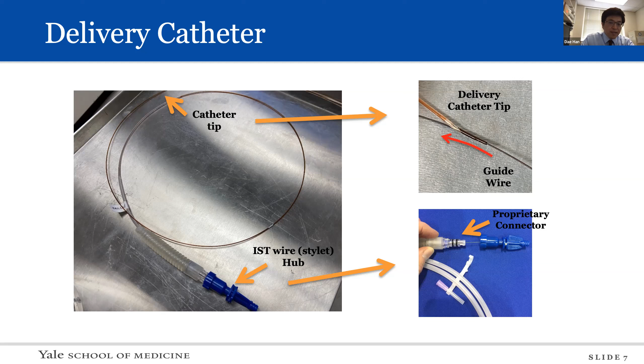And this is the operation mechanism. The delivery catheter has coaxial dual wall lumens. So when we press the syringe, water will push the source from the proximal to the distal direction, and once the source reaches the end of the catheter, there is a mesh structure that blocks the source, and the water can pass through the mesh structure and turn around to the outer lumen, and come back to the device.